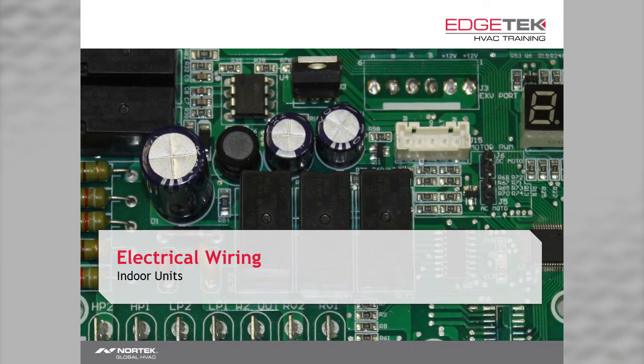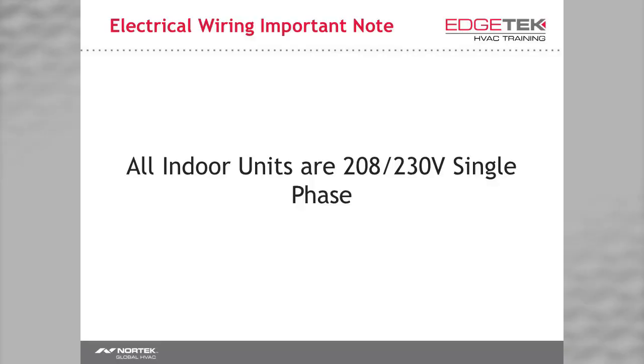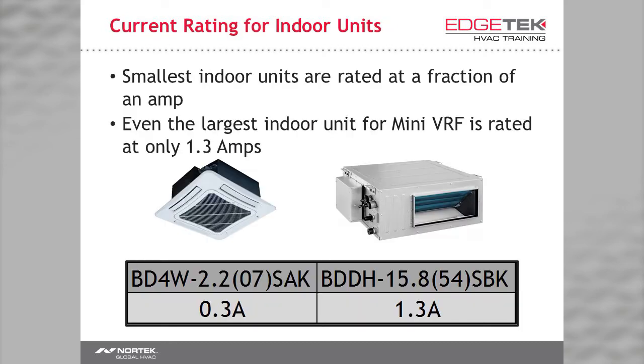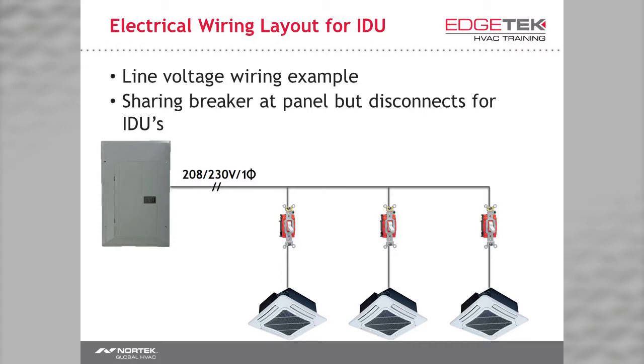Now that we've talked about physical installation and piping, let's talk about wiring. Always, always, always follow national, state, and local codes. All of our VRF indoor units are 208-230 single phase. Although you may not all be certified electricians, I have to point out that all of the indoor units have a very low current rating, as little as 0.3 amps and as high as 1.3 amps. What this can mean is that they could be wired to the same breaker with their own disconnect. They could be if your codes allow it.